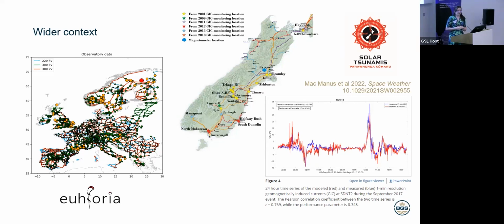The really interesting thing about the New Zealand grid is that Transpower have made available lots of GIC data from the grid, actual measurements of actual GIC going through transformers. All of those stars are places where they have been measuring GIC for some amount of time. You'll notice Halfway Bush near Dunedin is in red, that was one of the places that got GIC monitors put in after a transformer failed there, which kickstarted their interest from a space weather perspective.